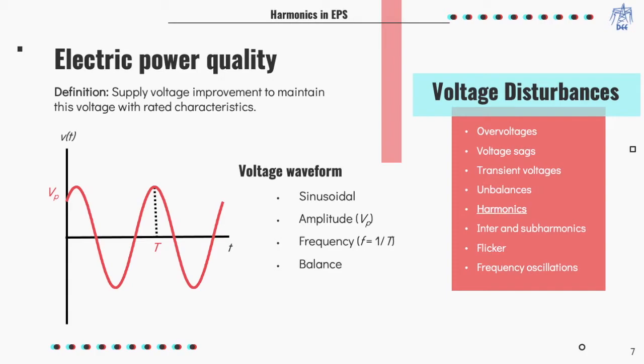Overvoltages are produced when the voltage is greater than the normal operating voltage of a device or circuit. A voltage sag at a point in the power grid is when the voltage of one or more phases suddenly drops below a set limit and recovers after a certain time, ranging from 10 milliseconds to several seconds. Voltage transients are defined as short-duration surges of voltage and/or current in an electrical circuit which has been disturbed. A three-phase system is unbalanced and/or asymmetrical when the magnitude of the three voltages and/or currents are not equal to each other, or the relative phase shifts between them are not equal to 120 degrees. Harmonics will be introduced in the next slide.